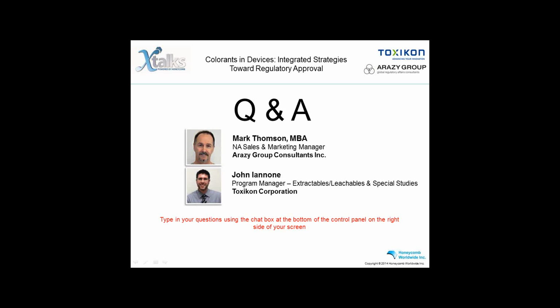Our next question, this audience member says, if I have a raw material declaration that the colorant has already been tested to ISO 10993, does that help? Well, it certainly helps to have some raw material testing, but when you take that raw material and you process it, and you form your device, and you may add other additives, and you do a certain sterilization process, the extractability, the leachability, even the compounds that will come out could potentially all change.